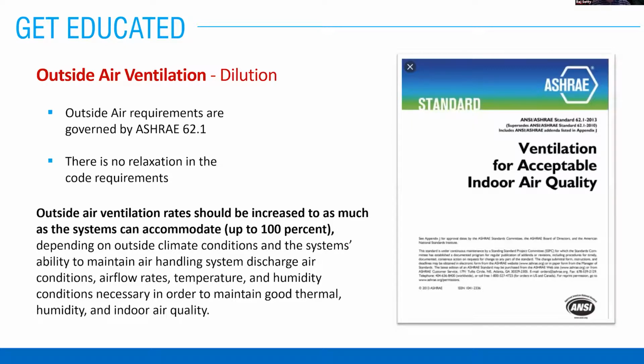The simplest way at times is to run your systems longer and use temporal strategies. If you're running them an extra hour, an extra 2 hours after the occupancy, that is allowing the classrooms and the offices to catch up. We're also running it between classes, and that allows zero quanta generation and the HVAC system to start to catch up and perform its dilution and filtration tasks.